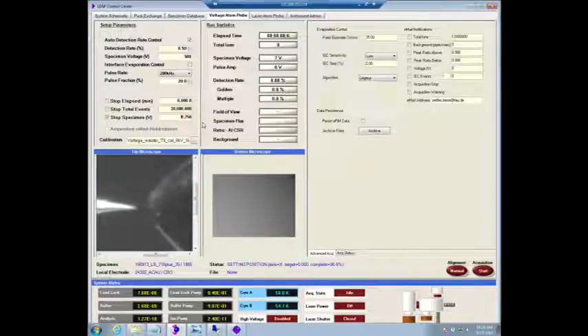Of course, if you've got a brand new atom probe that can do 2.5 kV pulsing, then you can go to a higher voltage. But on everything up to the 4,000 systems, that's the limit you have. The other reason why we usually limit experiments to that voltage is that the higher the bias voltage is, the more violent your specimen rupture will be. So if you've got a specimen rupture at 12, 13, 14 kV, it's very likely that it will take your local electrode into the grave with it, okay? And this would make your experiment a very expensive experiment.